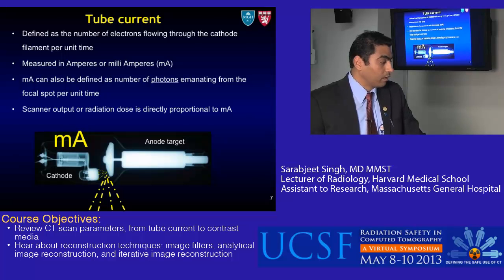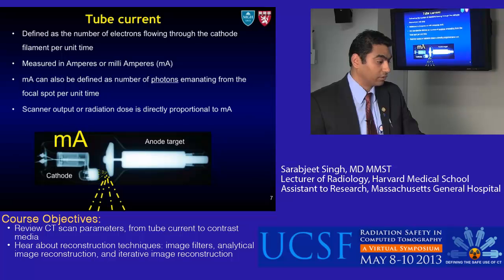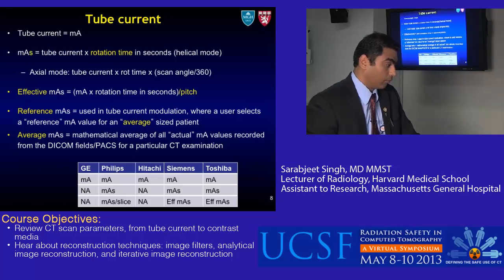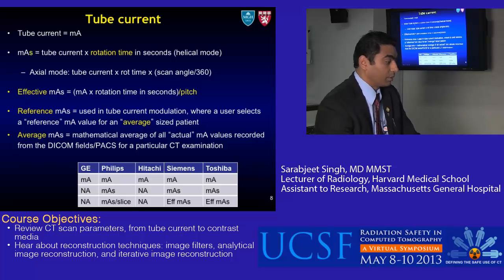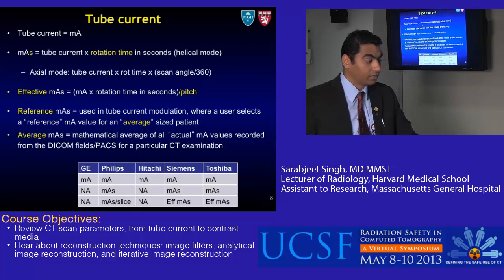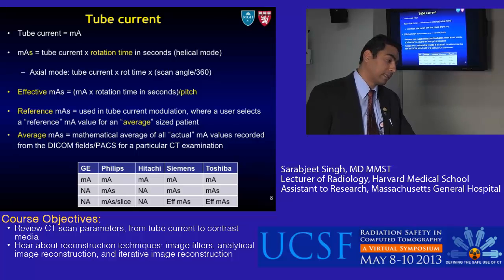Now let's look at tube current. Tube current is defined as the number of electrons flowing through the cathode filament per unit time, measured in amperes or in CT as milliamperes (mA). It can also be defined as the number of photons coming out of the focal spot per unit time — this is the scanner output or radiation dose, and it is directly proportional to the mA. A few related terms: mAs is tube current multiplied by rotation time in seconds in helical mode, or tube current multiplied by rotation time multiplied by scan angle divided by 360 degrees in axial mode.